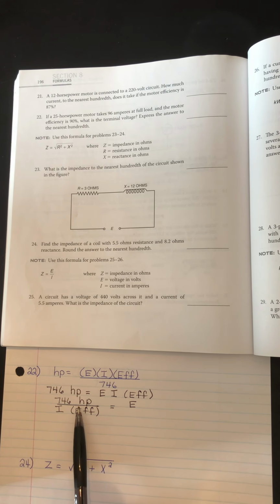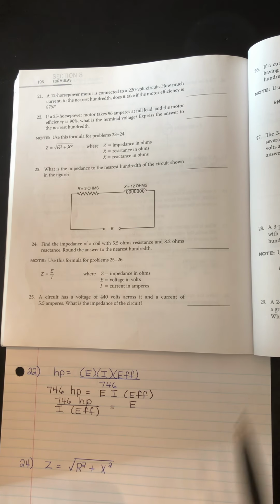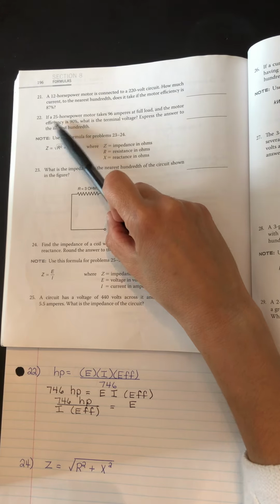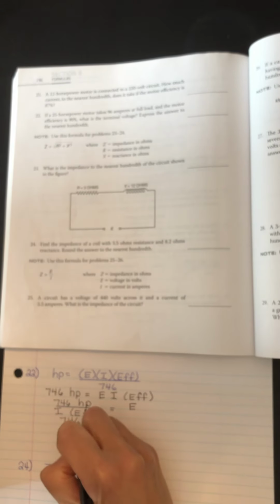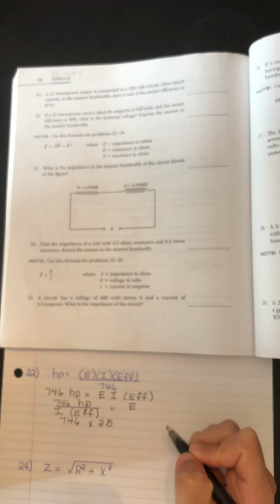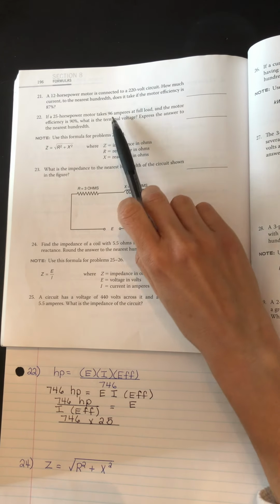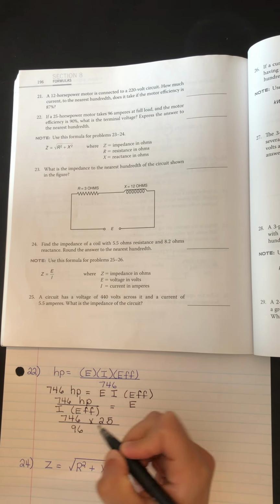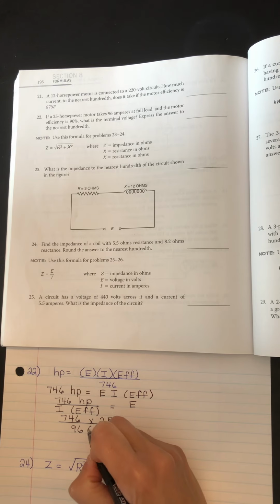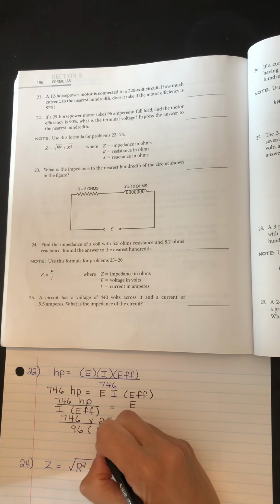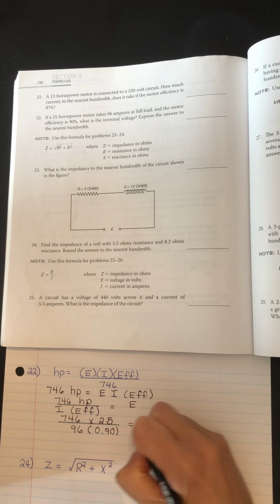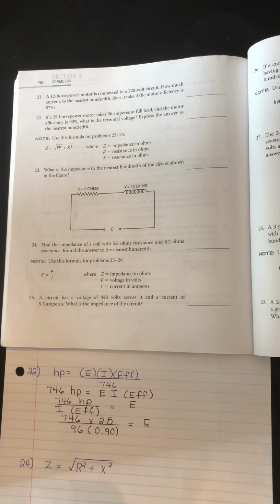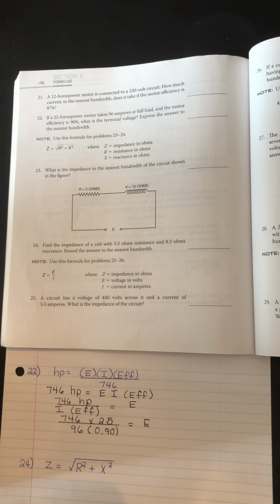Okay, so the power given in the question is 25. So we're going to take 746 and multiply it by 25. And then we're going to divide that by the current, which is 96. And also the efficiency, which is 90% or 0.9. Okay, so you can either first work out the top and the bottom and then do the division, or you can do it all in one step. So there are a number of ways you can do this, okay?